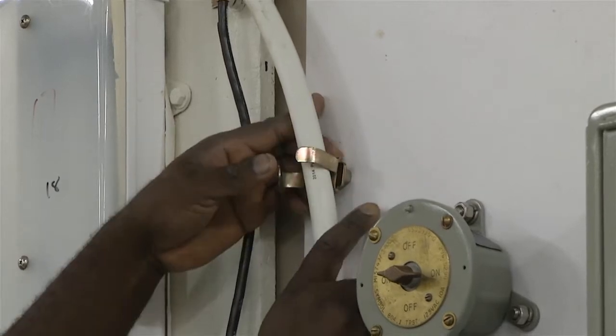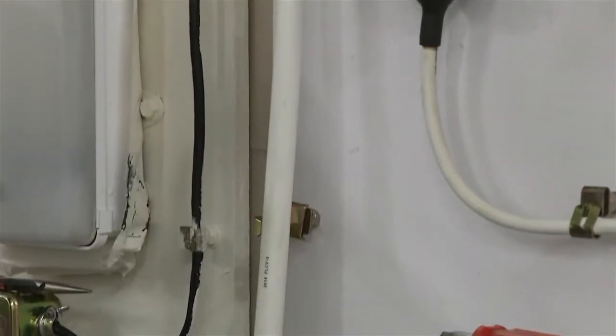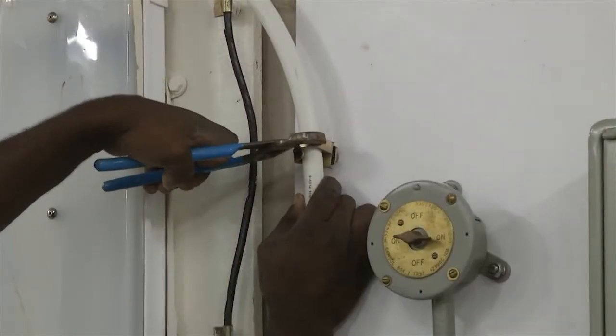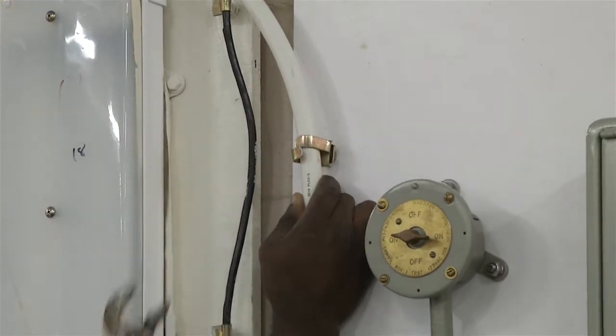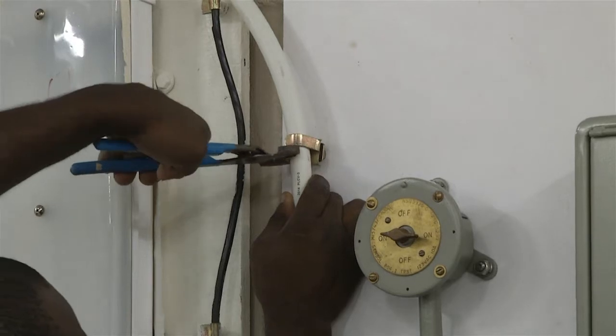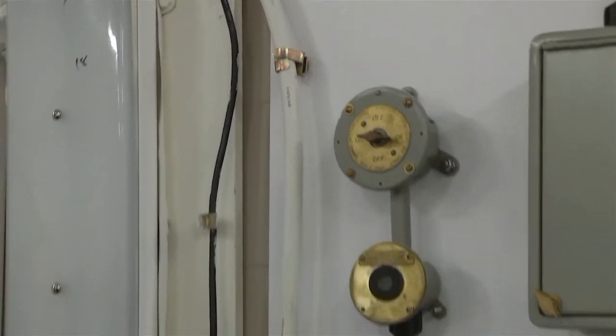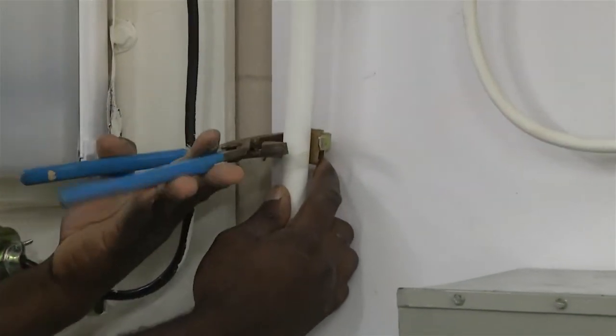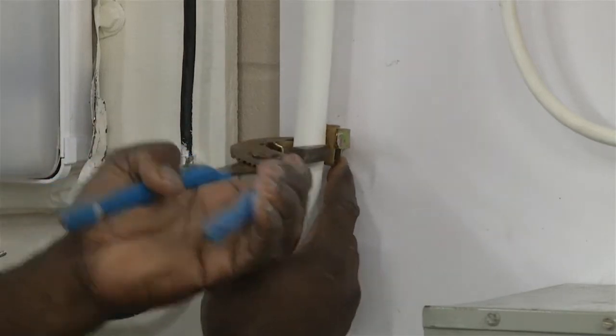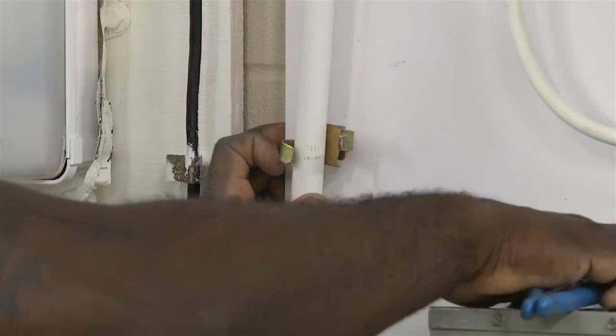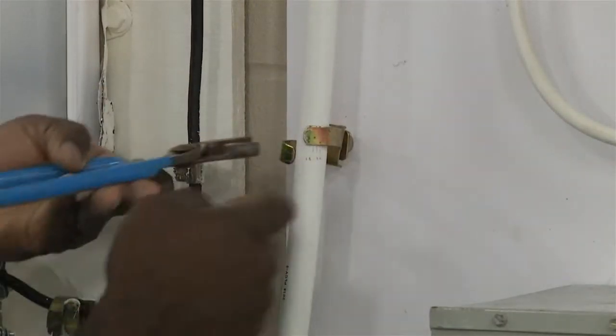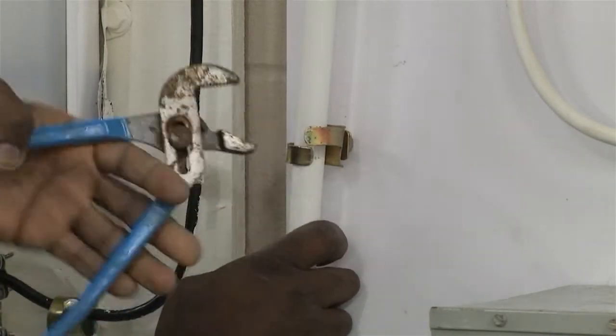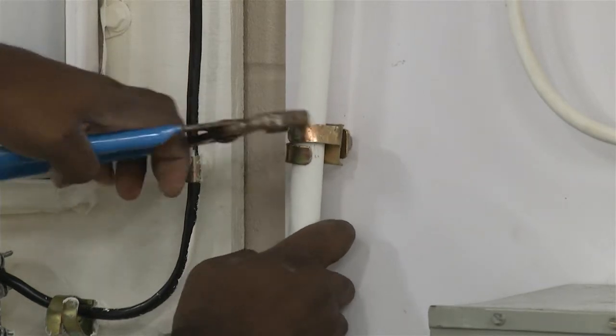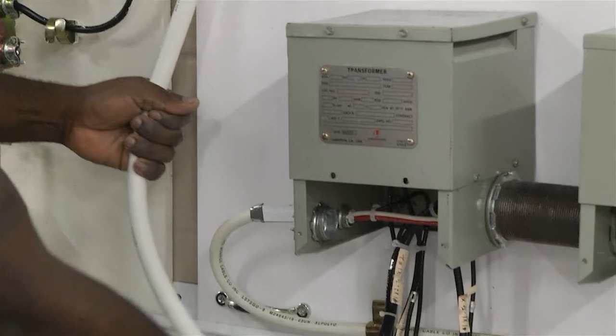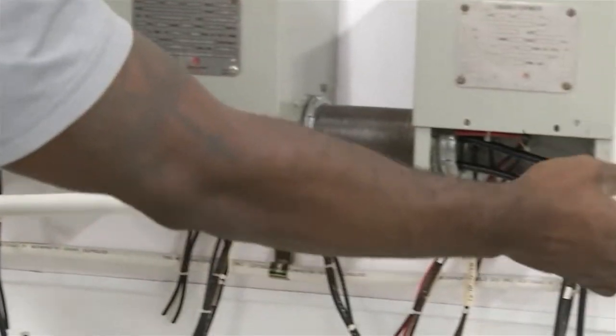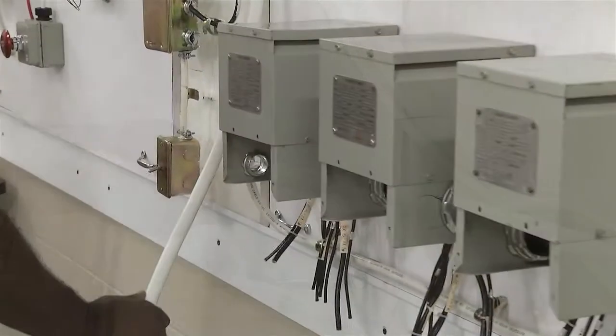Cables must be properly groomed in prior to hookup, and all clamps must be tightened. Ensure that the cable will not slip during hookup, causing the cable radius to be lost. Next, ensure that the cable has sufficient radius and length to cut in all 3 transformers, then cut off the excess.